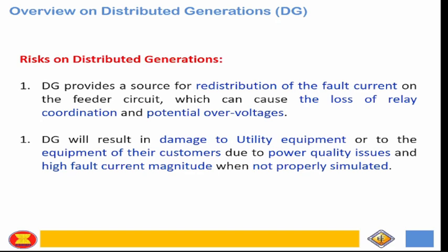DG provides sources of redistribution of fault current on the feeder circuit, which can cause loss of relay coordination and potential overvoltage. What is that scenario? Of course, some of the DG is connected through an interconnection transformer, and the grounding system of that transformer matters, especially if the primary is grounded and the secondary is delta. Your interconnection transformer will act as a grounding transformer. If we look at it in the sequence network, the grid is now in parallel, because the grid or the distribution system is normally solidly grounded through the substation.